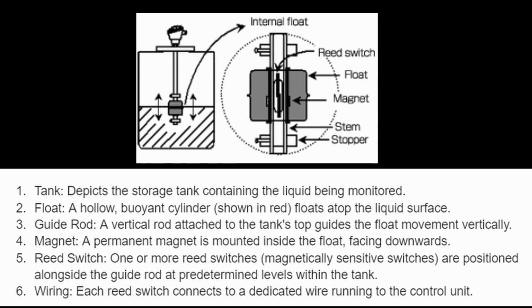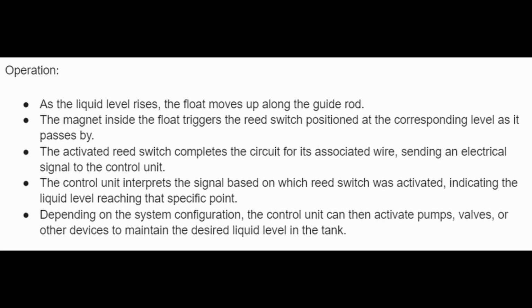5. Reed switch. One or more reed switches, magnetically sensitive switches, are positioned along the guide rod at predetermined levels within the tank. 6. Wiring. Each reed switch connects to a dedicated wire running to the control unit. 7. Operation. As the liquid level rises, the float moves up along the guide rod.